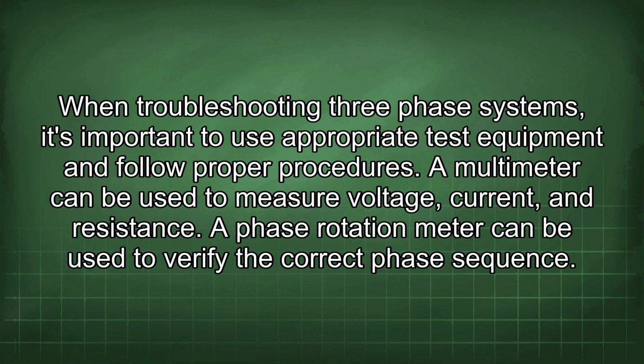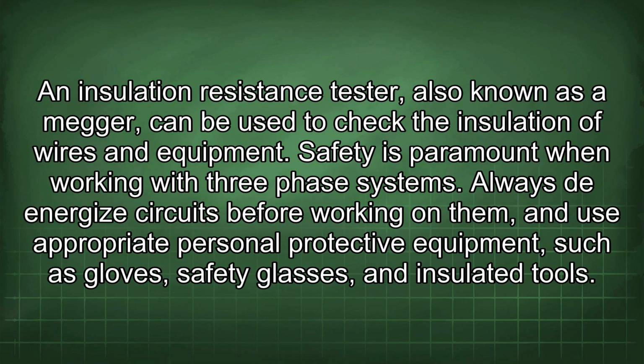When troubleshooting three-phase systems, it's important to use appropriate test equipment and follow proper procedures. A multimeter can be used to measure voltage, current, and resistance. A phase rotation meter can be used to verify the correct phase sequence. An insulation resistance tester, also known as a megger, can be used to check the insulation of wires and equipment.